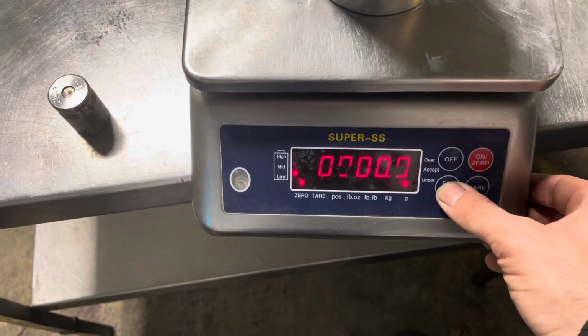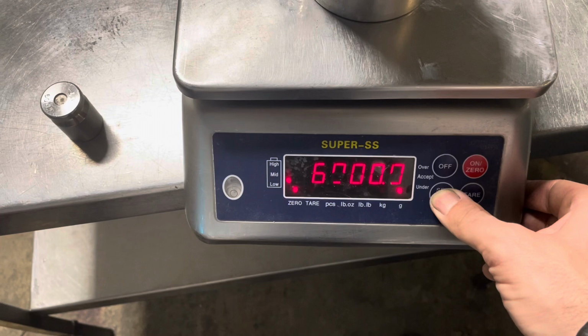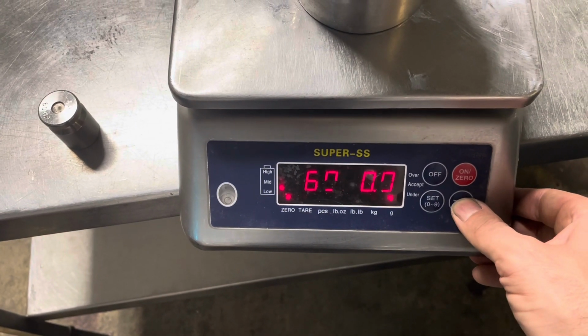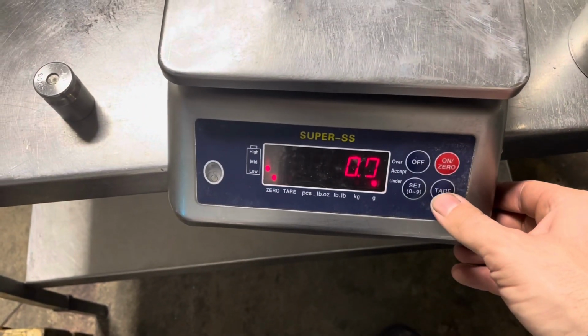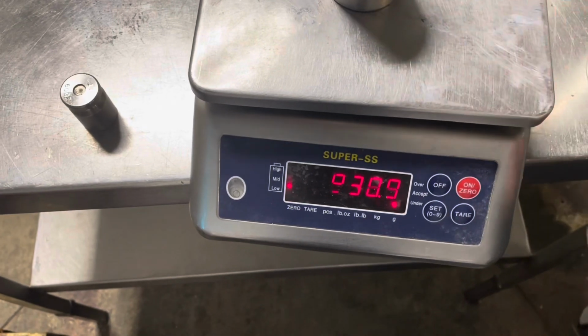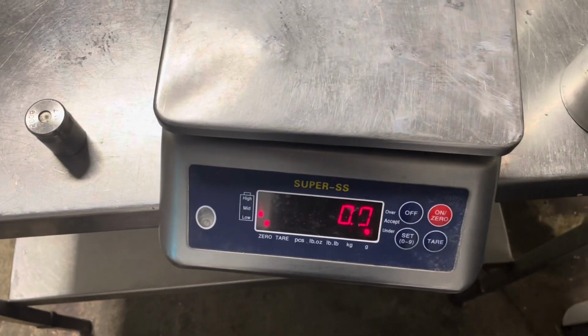And that's just because the load cell is worn. It could be dropped, it could be heated. That does happen to scales too, because they'll lose the bridge in this load cell, but I'm digressing. Anyways, single point doesn't work for the scale. So we're next going to do a linear calibration.